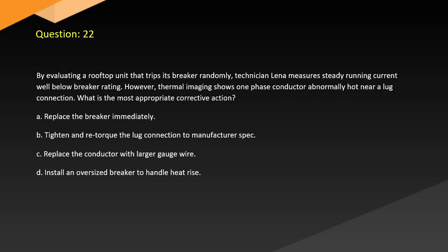Question 22. By evaluating a rooftop unit that trips its breaker randomly, a technician measures steady running current well below the breaker rating. However, thermal imaging shows one phase conductor abnormally hot near a lug connection. What is the most appropriate corrective action? A. Replace the breaker immediately. B. Tighten and retorque the lug connection to manufacturer spec. C. Replace the conductor with larger gauge wire. D. Install an oversized breaker to handle heat rise.